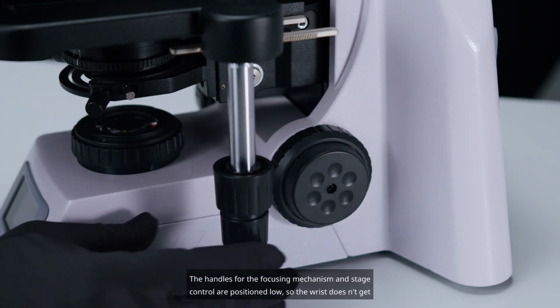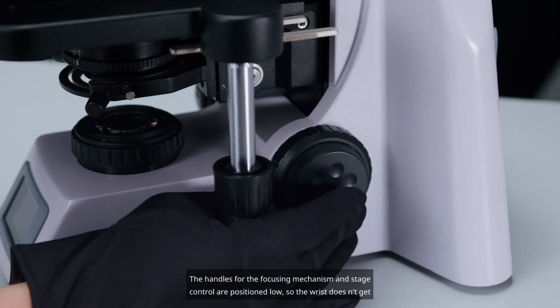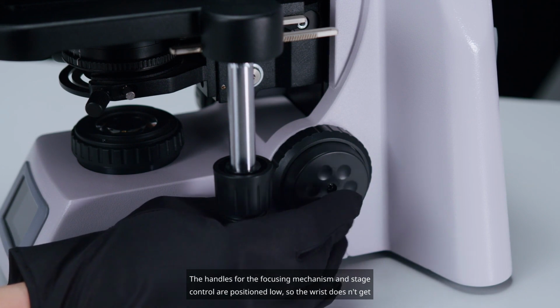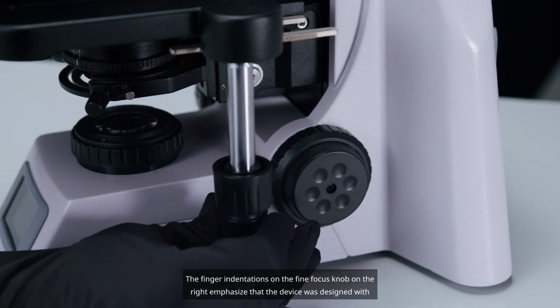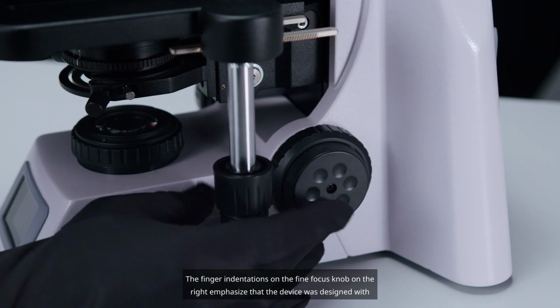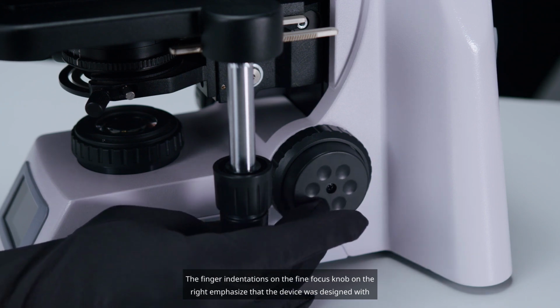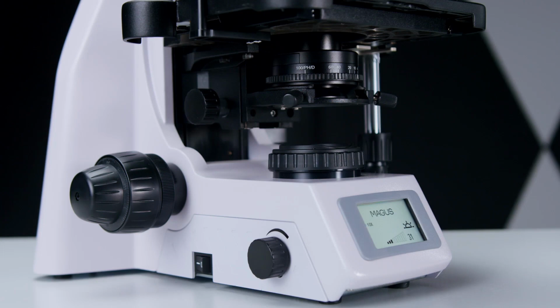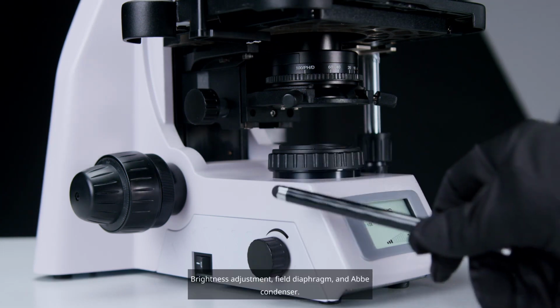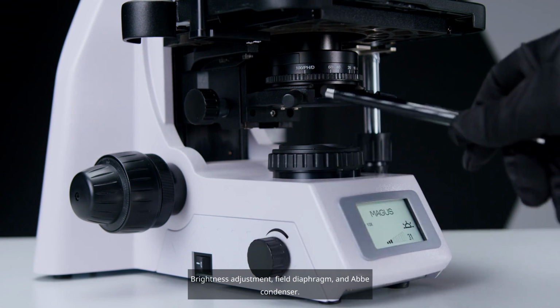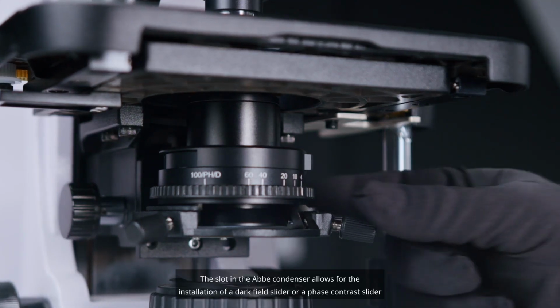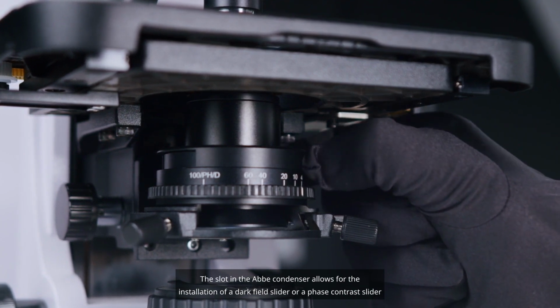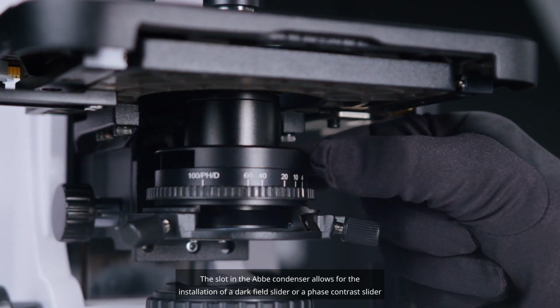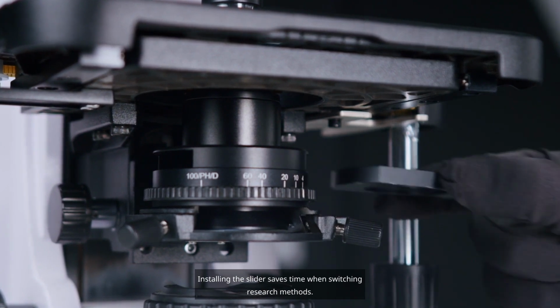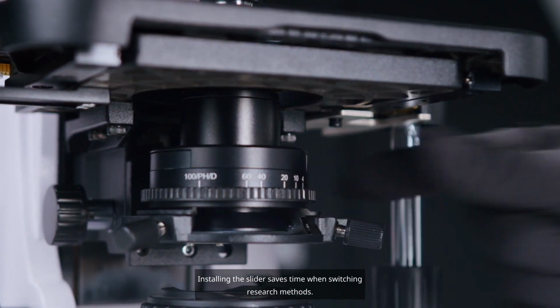The handles for the focusing mechanism and stage control are positioned low, so the wrist doesn't get strained. The finger indentations on the fine focus knob on the right emphasize that the device was designed with attention to detail. The light control handles are located in a single working area. Brightness adjustment, field diaphragm, and Abbe condenser. The slot in the Abbe condenser allows for the installation of a dark field slider or a phase contrast slider. Installing the slider saves time when switching research methods.